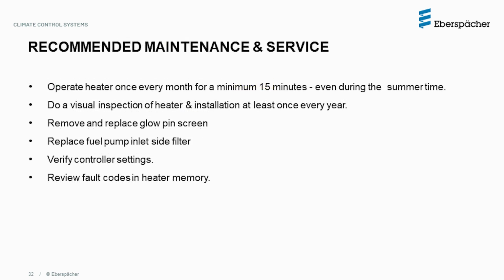The annual maintenance and service recommendations are very similar to what is recommended on the first generation Airtronic heater. The most important recommendation is to operate the heater with maximum set point temperature once every month and for a minimum of 15 minutes each month, all year long. A complete visual inspection of the heater and installation must be done once every year, preferably before the heating season. It is recommended to remove and replace the glow pin screen every year or after every 1,000 hours of operation. This process allows you to clean up any carbon residue that may be blocking the ventilation hole.